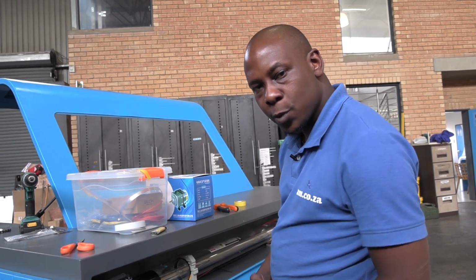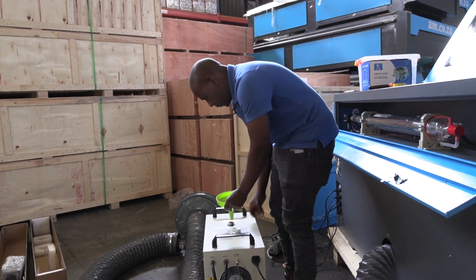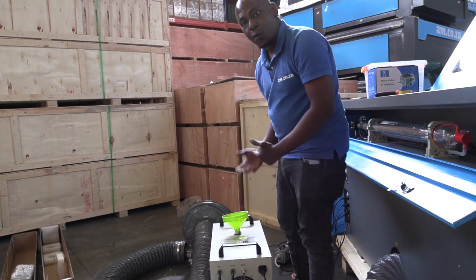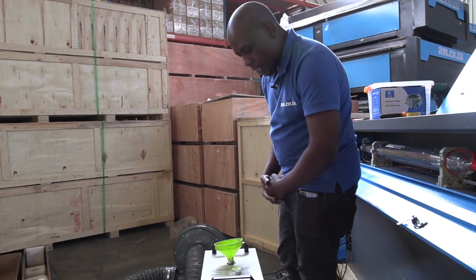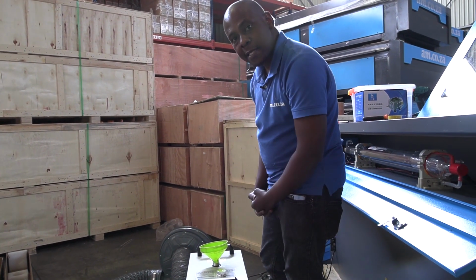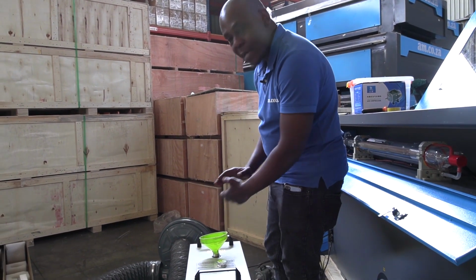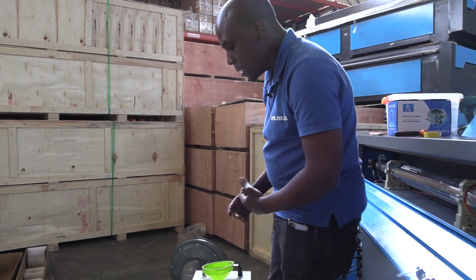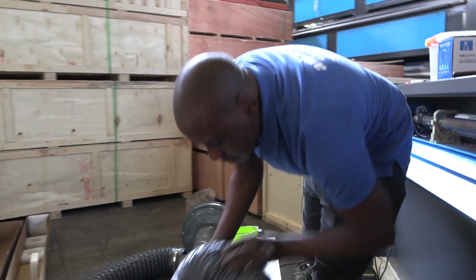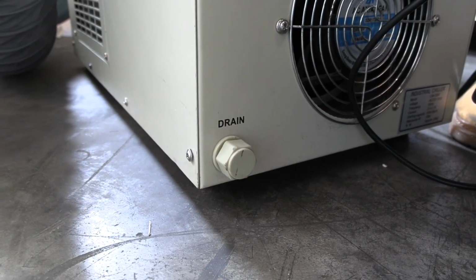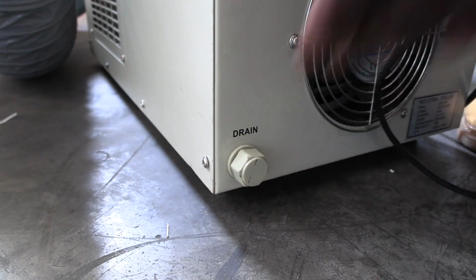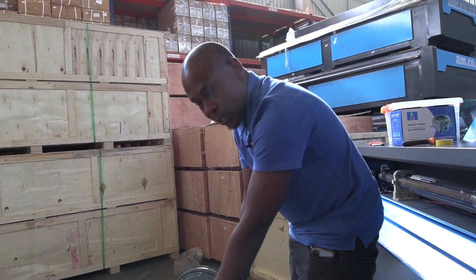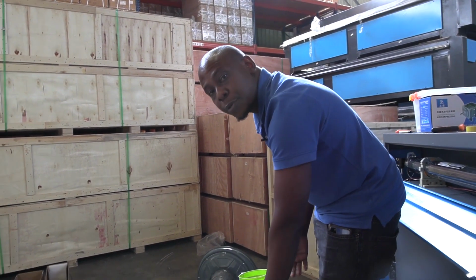Now we move on to pouring our distilled water into our water chiller. So for a new installation, on a water chiller, we normally test this at our factory. So it might contain a little bit of water inside. So what you may want to do is open the drain, check if there's any water inside, close it tight, pour in a little bit of tap water just to rinse it out and drain again, close, and then you're good to go to pour in your distilled water.